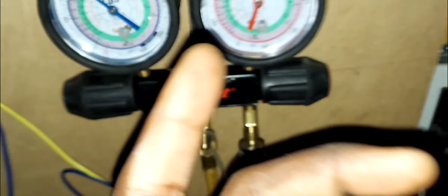In a worst case scenario, you can bypass this switch in an emergency, but for the high pressure switch, I don't recommend it. Go get the part. Bypassing it didn't solve the problem, and it creates liability as well.